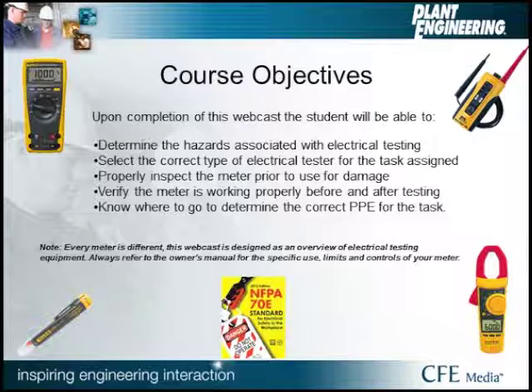Our course objectives today start off with the determination of the hazards that are associated with electrical testing. We also want to cover the selection of the correct type of electrical tester, and that's going to be dependent on the task that you're assigned. We want to properly inspect our meters prior to use to make sure that they're not damaged. We want to verify that our meter is working properly both before and after our test. We want to know where to go to determine the correct PPE for the task. And we're going to be using the NFPA 2012 edition as our guide for this information.